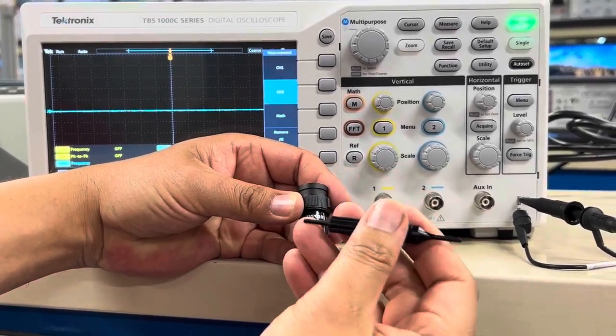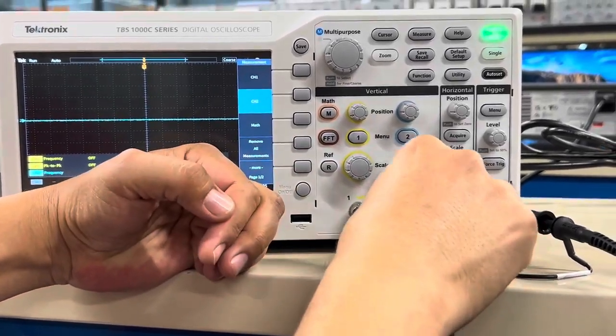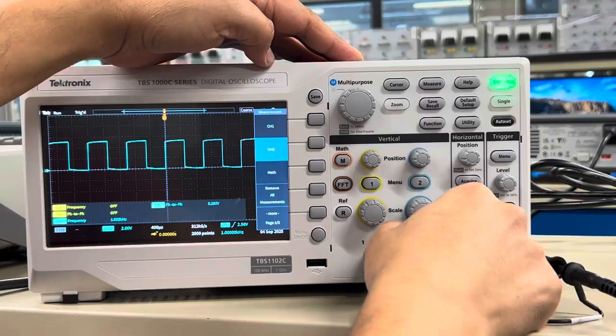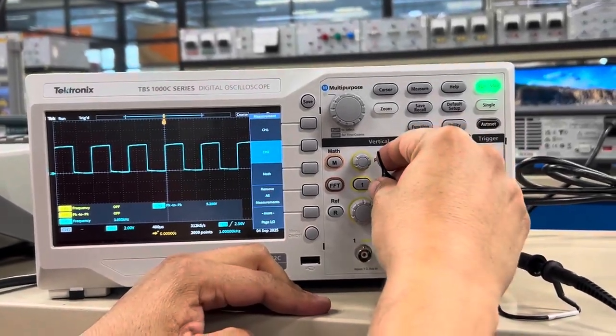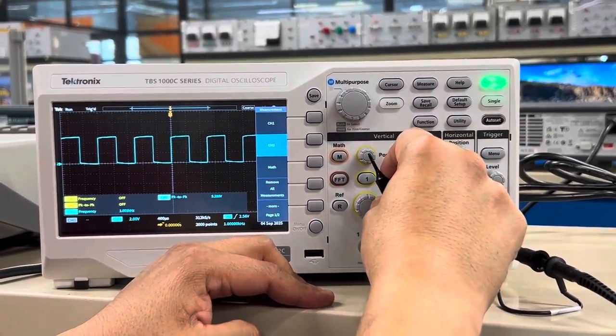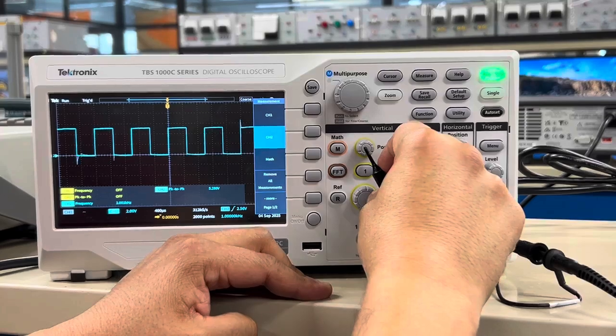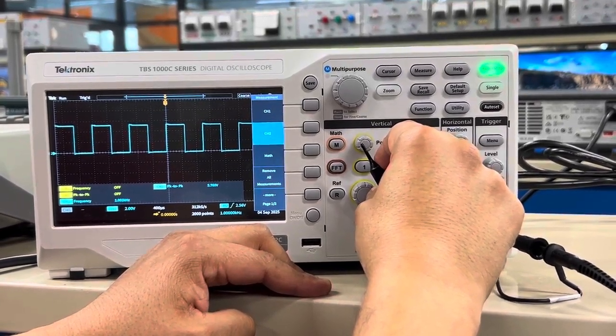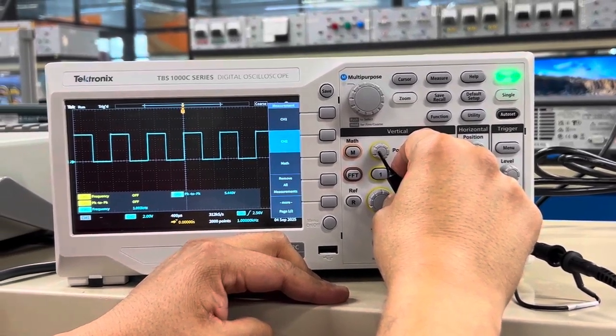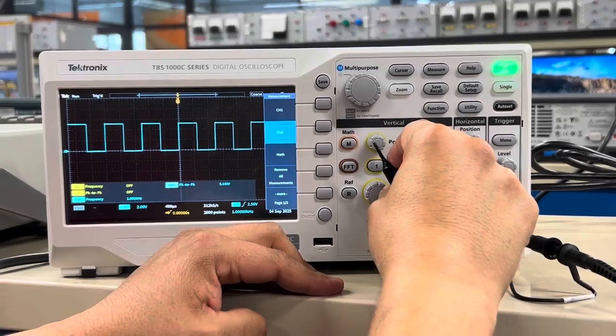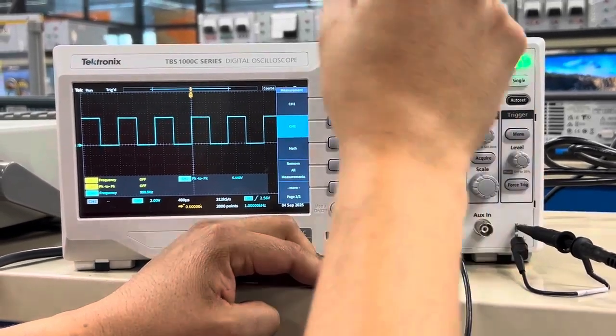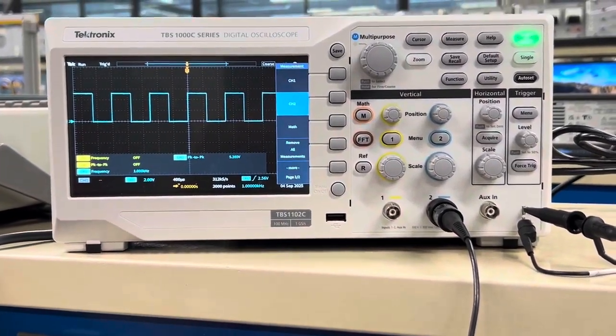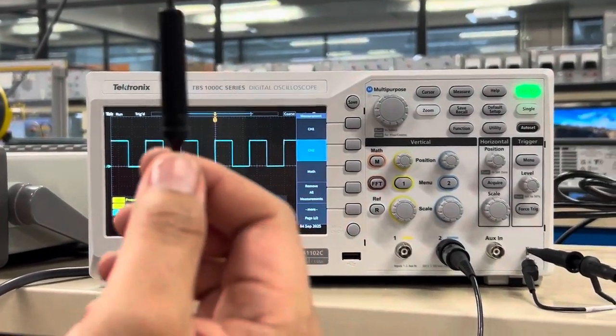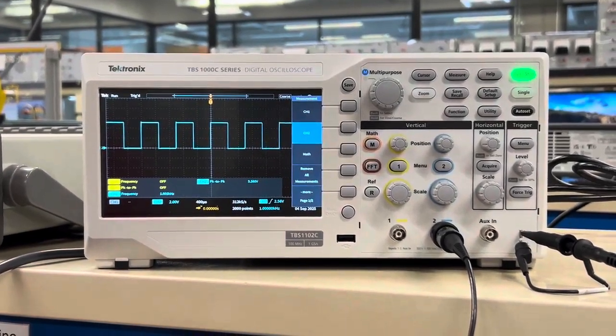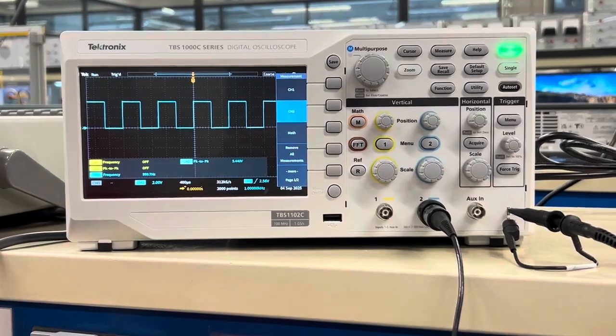We will put the flat side of the screwdriver. We'll have to do it live. That's the only way to know if we're doing the proper calibration. So we'll put it here, and as we rotate clockwise or anti-clockwise, the signal will be fixed. We aim to get the best shaped signal possible. I'm going to leave it there. That can probably be corrected more. I just wanted to show you that the probe can be fixed with this screwdriver. What we're fixing is actually a part of the probe, which is the coupling capacitance.